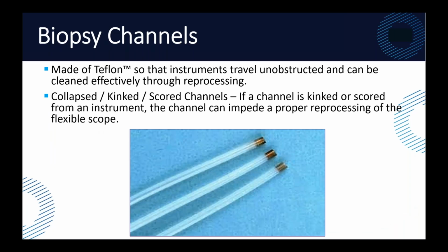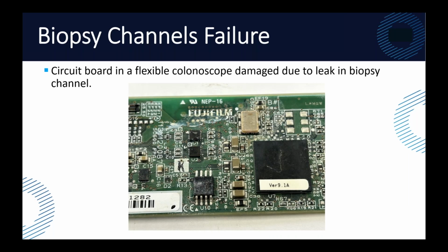Biopsy channels. This is specific to endoscope. Ultrasound TEEs do not extract biopsies at all. So these are the kind of things that have to be cleaned very well during reprocessing. And anytime you have a collapsed or kinked or scored biopsy channel, it presents a problem that could occur certainly as it's being cleaned, or even in a patient. Or it's being cleaned and there's a break in the biopsy channel, and literally the liquid goes into the endoscope and doesn't come back out. So, which is going to always cause a problem. Here's a circuit board that actually was damaged due to a leak in a biopsy channel. You can see all the various water damage throughout that.